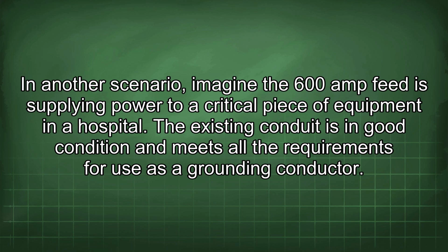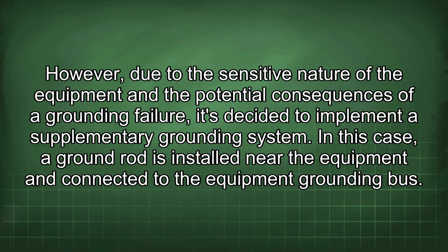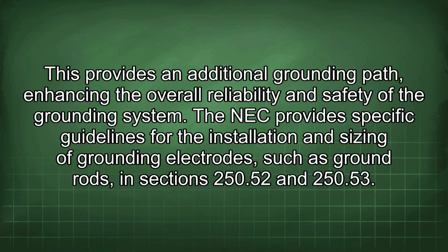In another scenario, imagine the 600 amp feed is supplying power to a critical piece of equipment in a hospital. The existing conduit is in good condition and meets all the requirements for use as a grounding conductor. However, due to the sensitive nature of the equipment and the potential consequences of a grounding failure, it's decided to implement a supplementary grounding system. In this case, a ground rod is installed near the equipment and connected to the equipment grounding bus. This provides an additional grounding path, enhancing the overall reliability and safety of the grounding system.